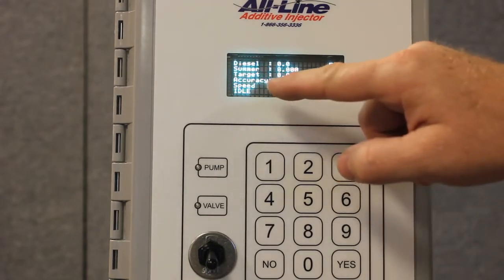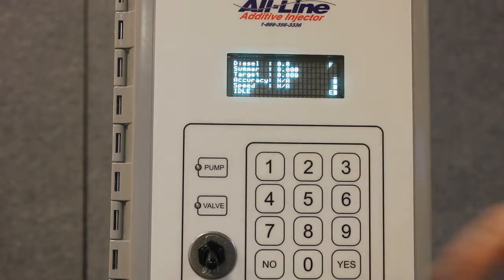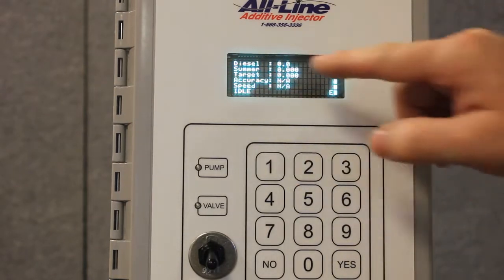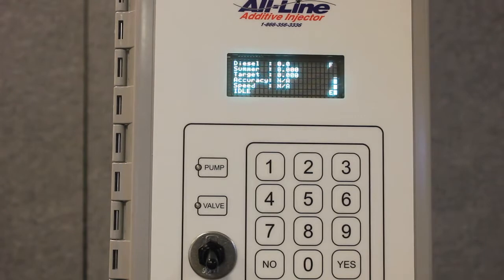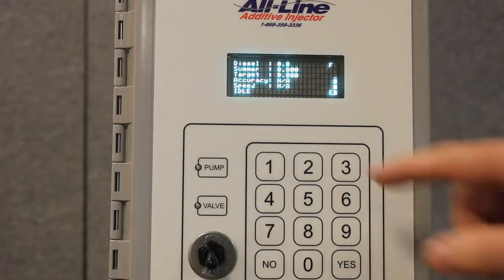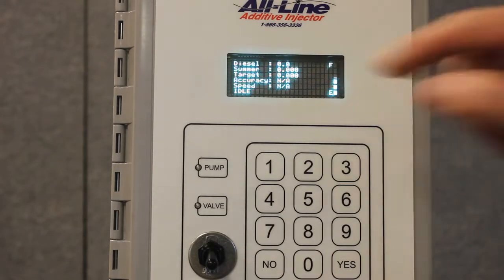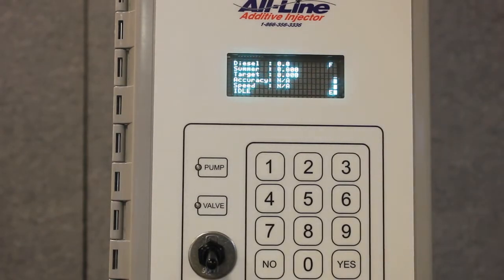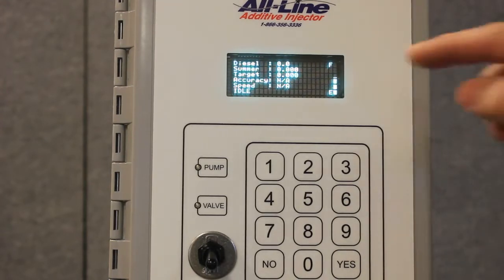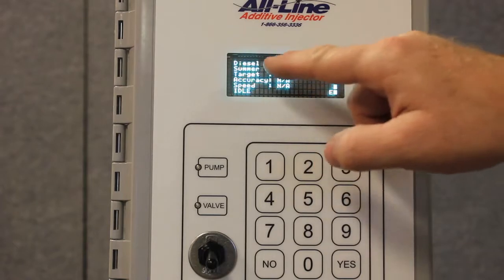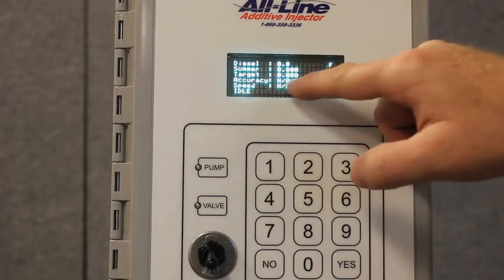So, if I've done 1,000 gallons of diesel, the target often will be 1.000 because most additives are 1 to 1,000. The entry that says the additive name hopefully also says 1.000, but it might say something slightly different, 0.985 or 1.004. Those two numbers will be used to calculate the accuracy.